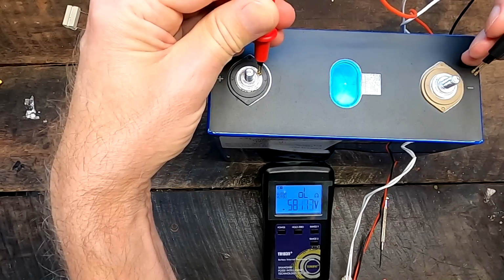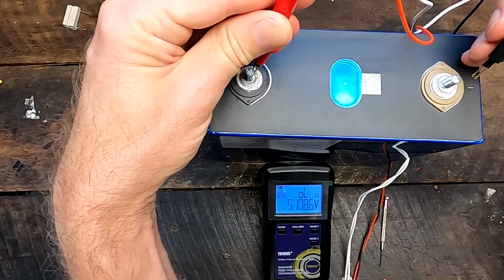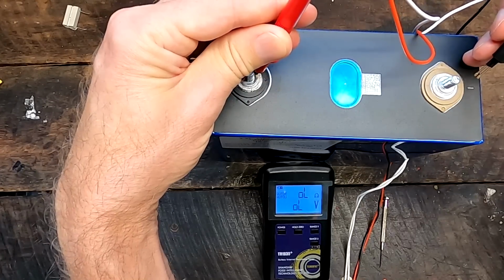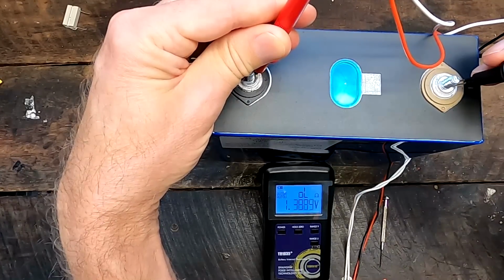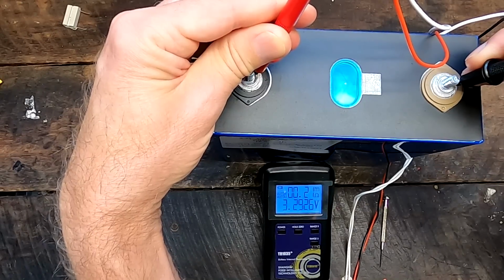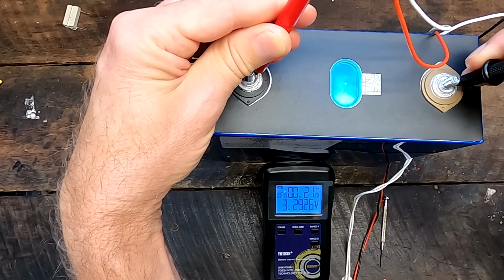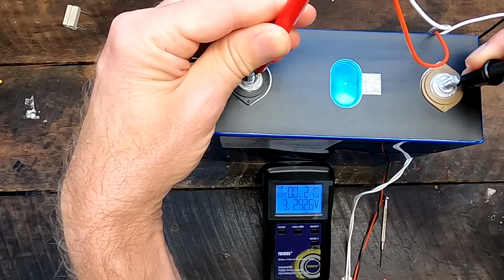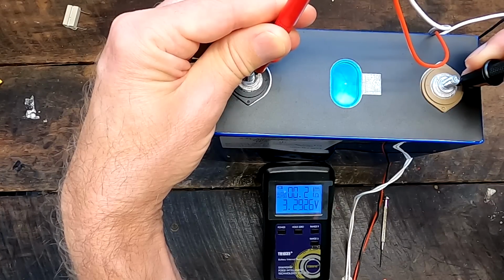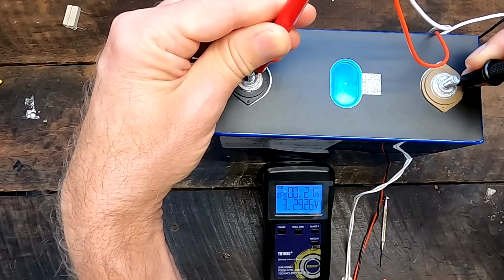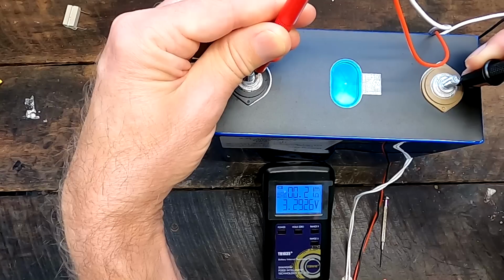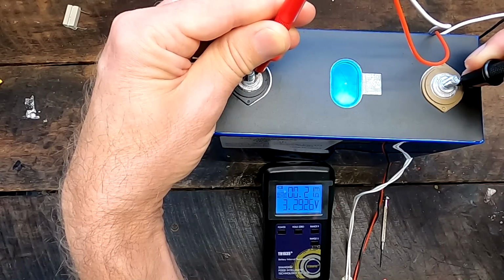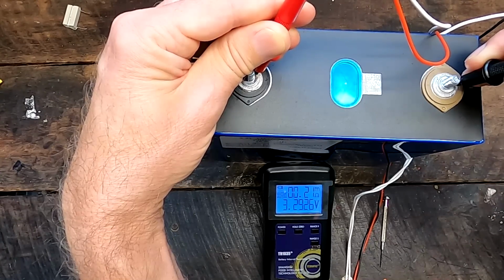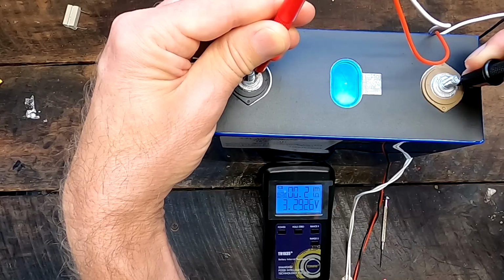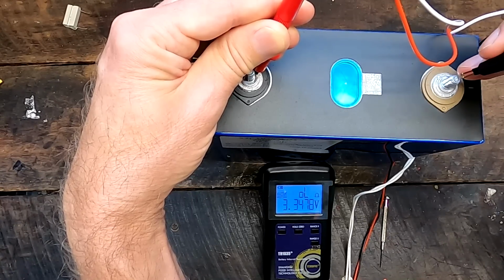Second measurement is from the top ring, the polished ring where the bus bar sits and has contact with the terminal, on both sides again. We get 0.21 milliohms — exactly as stated on the label. So obviously this is the internal resistance they're measuring, and as you can see, we're adding another 0.45 milliohms when including the studs.